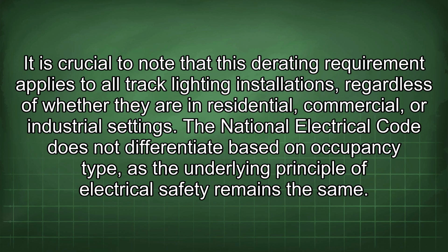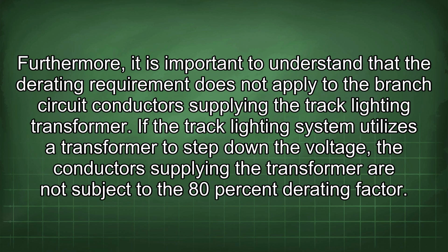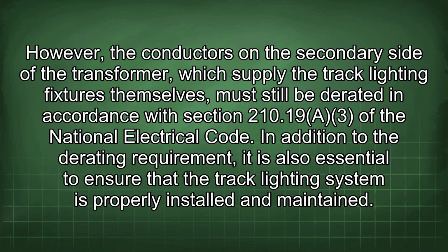The National Electrical Code does not differentiate based on occupancy type, as the underlying principle of electrical safety remains the same. Furthermore, it is important to understand that the derating requirement does not apply to the branch circuit conductors supplying the track lighting transformer. If the track lighting system utilizes a transformer to step down the voltage, the conductors supplying the transformer are not subject to the 80% derating factor. However, the conductors on the secondary side of the transformer, which supply the track lighting fixtures themselves, must still be derated in accordance with Section 210.19 A3 of the National Electrical Code.